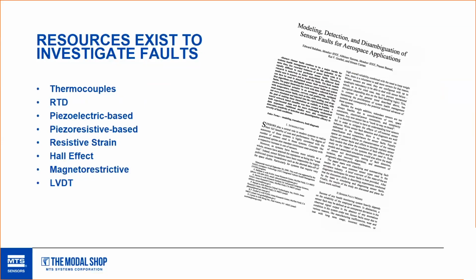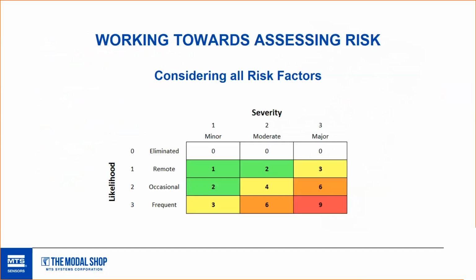So working towards the sensor risk, you really have to consider all the factors. Who has dropped an accelerometer in the past? A story that I love to give: one time when I was visiting a large facility, a metrology engineer and I were talking, and we were leaving the metrology room, and ahead of us about 30 feet was an instrument cart that had just left the cal lab. Three sensor cases fell off the cart onto the concrete walkway, and the person operating the cart just picked them up, put them on the cart, and started walking away. The engineer hosting my visit didn't really seem to notice, and we almost walked around the cart before I asked the question, well, what happens to these sensors now? I didn't learn the type of sensor that was used, but in my experience dealing with highly sensitive accelerometers for the past 30 years, it kind of preconditioned my brain to recognize that those sensors should be retested.